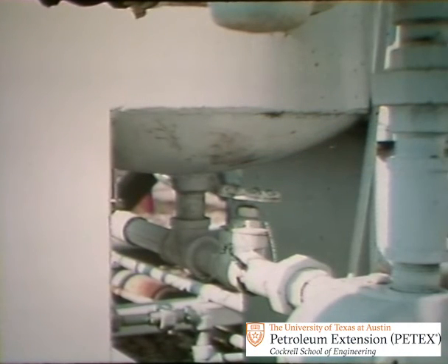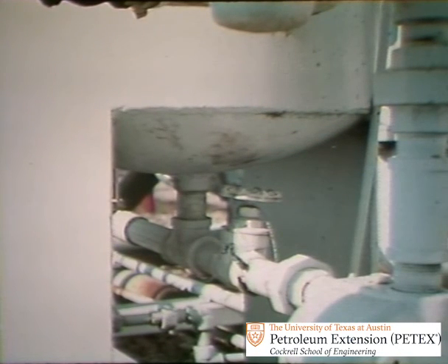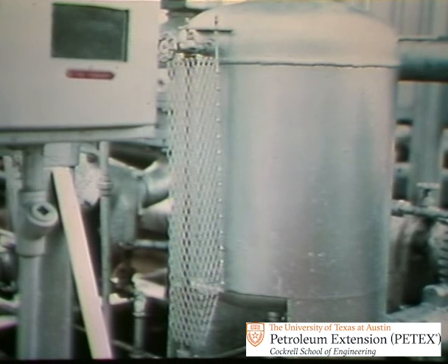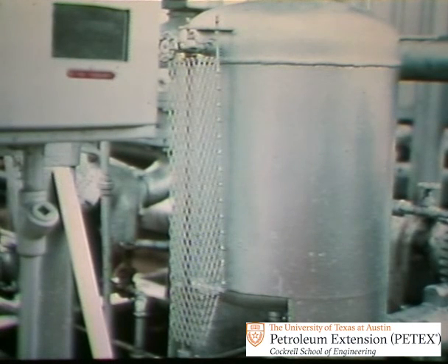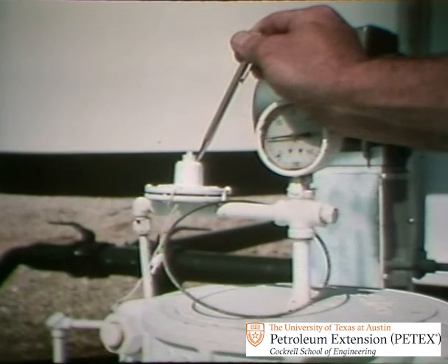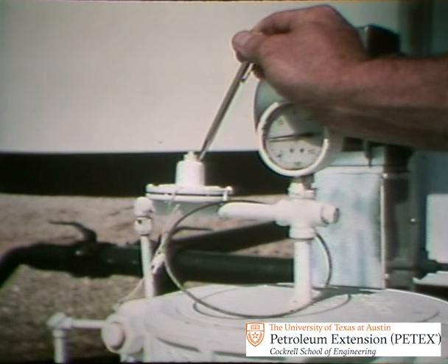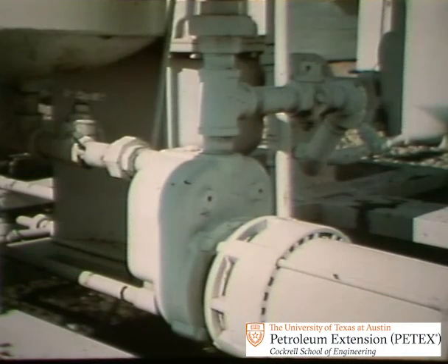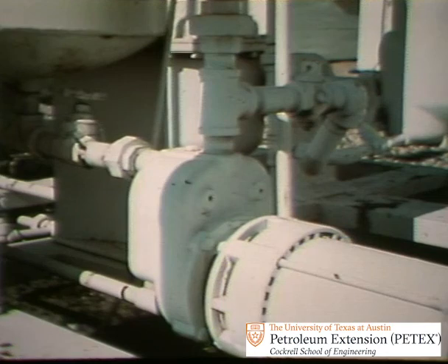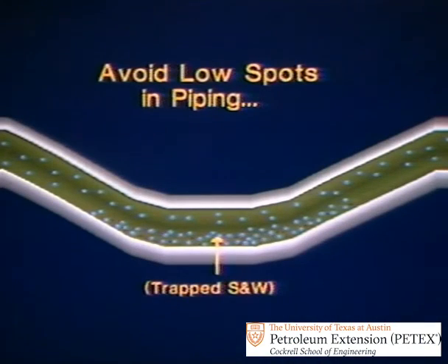The receiver should have a sloping bottom, and it should be coated with acrylic or phenolic paint inside. Use the gauge glass to determine if a sample is being collected. A pressure relief valve should be installed on the receiver to protect it and maintain enough pressure to minimize evaporation loss. Use a power-driven mixing device to properly mix the sample. Arrange all piping so that there are no low spots that could trap S&W.